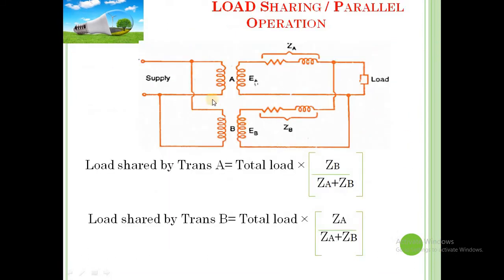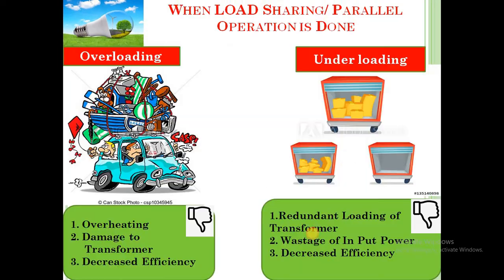Now next is how transformer A and transformer B share the load. Here the circuit diagram is the same. The load shared by transformer A is equal to the total load into ZB upon ZA plus ZB. Now the load shared by transformer B is equal to the total load into ZA upon ZA plus ZB. So this is the formula to find out how much load is shared by transformer A and transformer B.